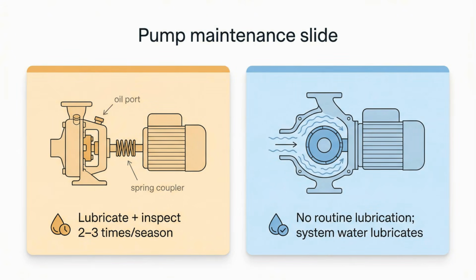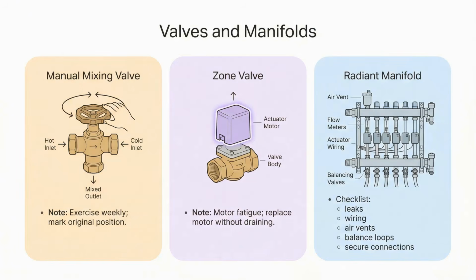Pump maintenance depends on pump type. Older pumps may require bearing or bushing lubrication and inspection of the spring coupler a few times during the heating season. Newer wet rotor circulators use system water for lubrication and typically need no routine maintenance, assuming correct installation and good water quality. Manual mixing valves can seize from poor water quality and lack of use, so exercising them regularly, about weekly, helps, and marking the original handle position ensures it goes back where it was. Zone valves usually require little maintenance. They cycle a lot and eventually the actuator motor fails, and the common fix is simply replacing the motor without shutting down or draining the system.